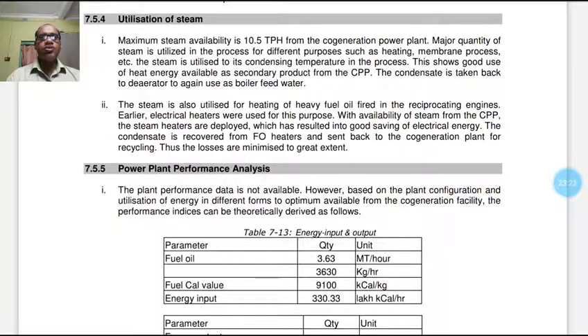The steam is also utilized for heating of heavy fuel oil fired in the reciprocating engine. Earlier, electrical heaters were used for these purposes. With availability of steam from the CPP, steam heaters are deployed, which has resulted in good savings of electrical energy. The condensate is recovered from the FO heater and sent back to the cogeneration plant for recycling. Thus, the losses are minimized to a great extent.